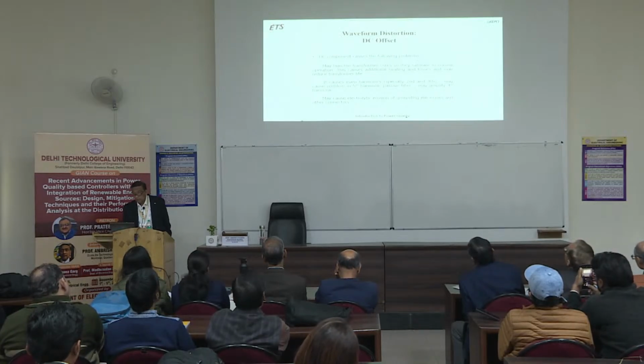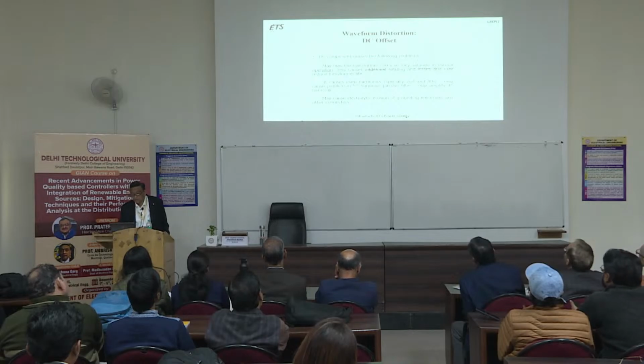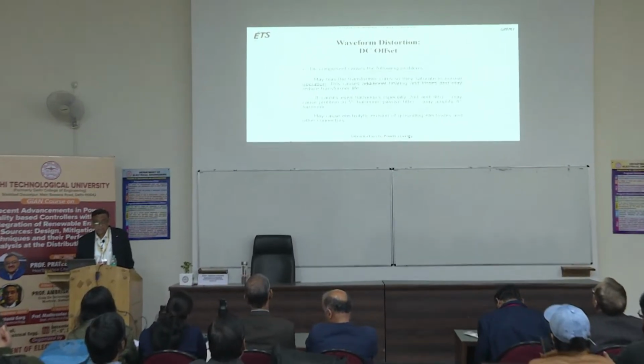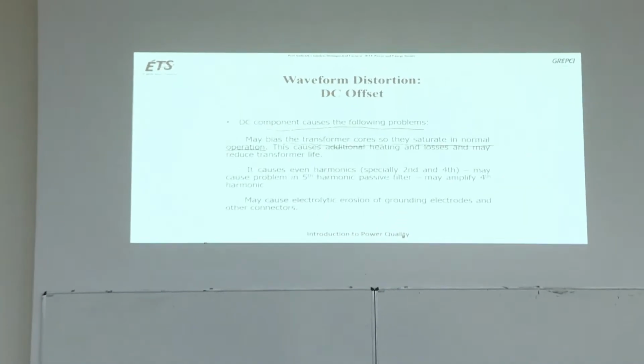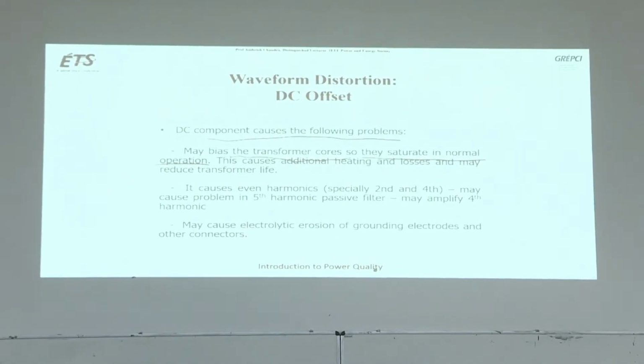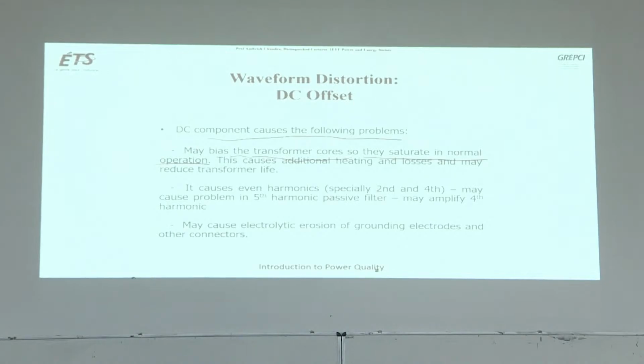DC component causes the following problems. It may bias the transformer core so that it saturates in normal operation. So basically you have to derate the transformer. If the core is saturated, you cannot run the transformer at 100% load. You may have to derate it, otherwise it may heat up because of the additional losses and reduce the transformer life.